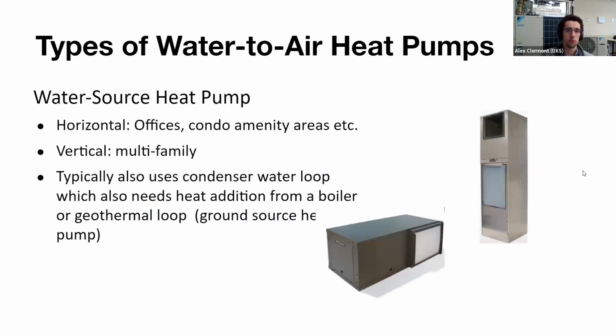Next, I didn't talk about these water source heat pumps, so next we'll get into water source heat pumps, which are, again, water to air. And as I previously mentioned, these are the most common type of water source heat pump machine. They do come in various different sizes and capacities. And here on the right, we see a horizontal water source heat pump, which you would often see in a commercial office building, for example. Vertically on the rightmost would often be seen in a multi-family application.